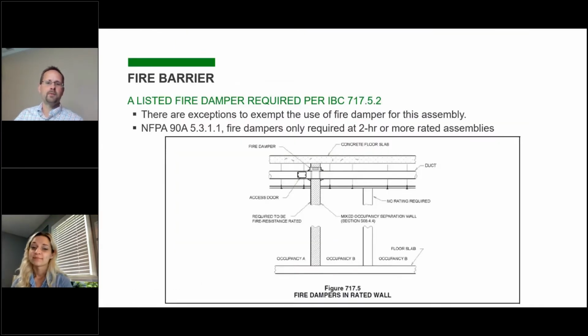So fire barriers, I think, are the most difficult to decide how to attack from a mechanical perspective. Number one, depending on what the application of that particular fire barrier is, your application of dampers will be different. For instance, as Glynis said, these could be a shaft. Well, if you have a shaft, the building codes say you need a fire smoke damper with some exceptions on a shaft. And we'll talk more about shafts later, so I'm not going to go into a lot of detail on that right now. If it's an exit passageway or a stair, you really can't penetrate that at all, even with a fire damper, because a stairway can only be served from a system that's dedicated to that stairway, and same with an exit passageway. So if you see it in that application, you've got to make sure you keep all your other systems out of that assembly.